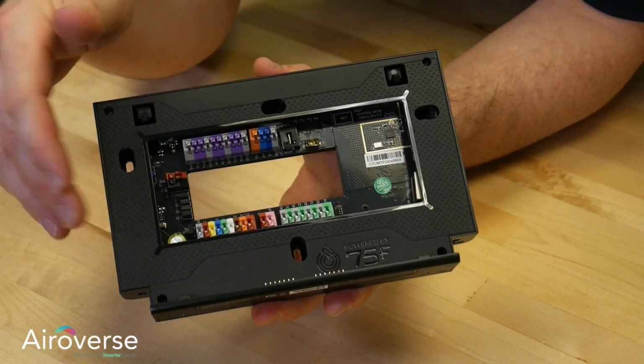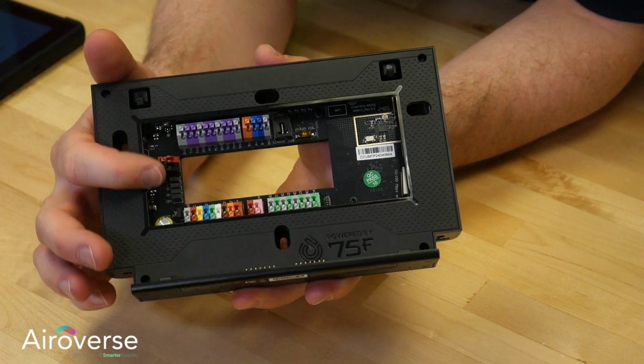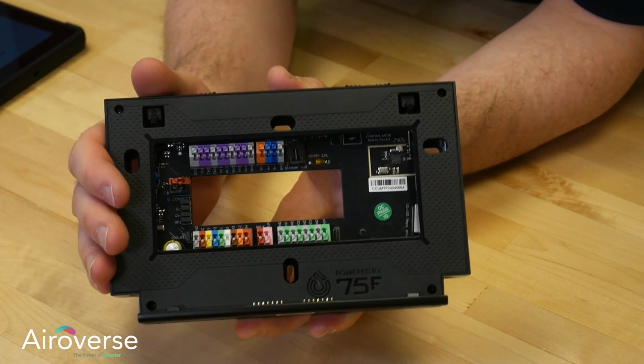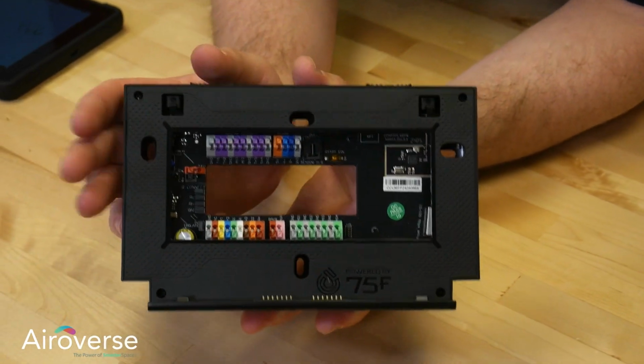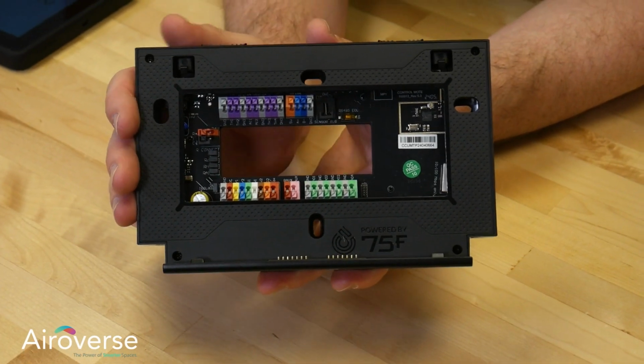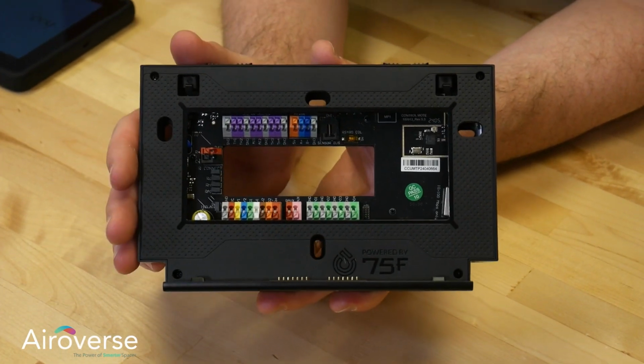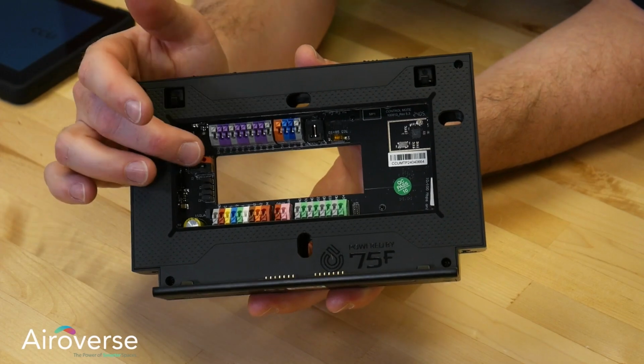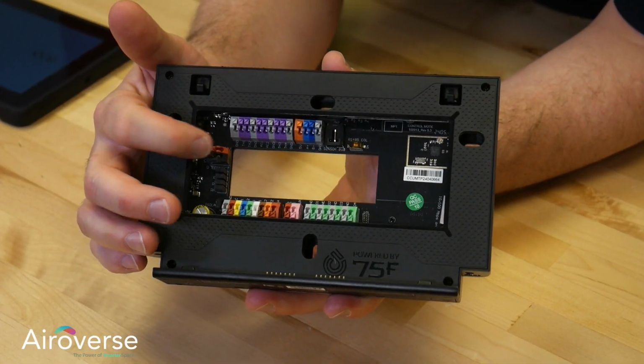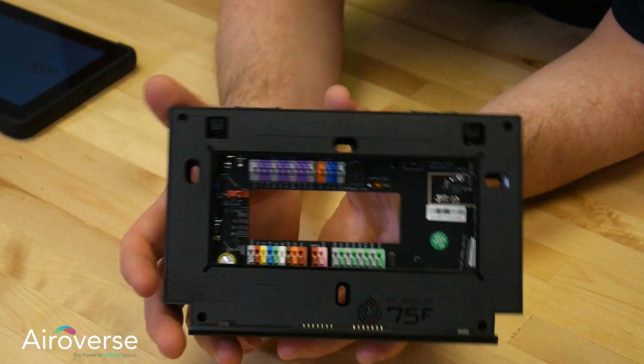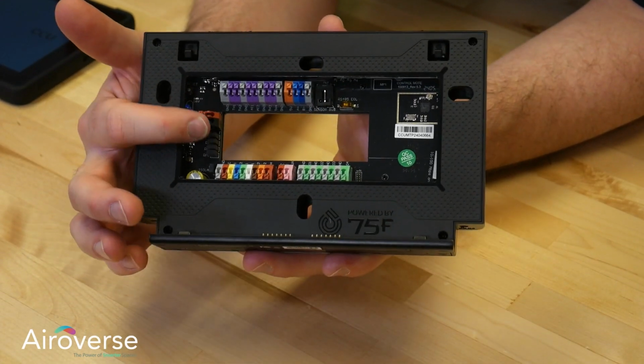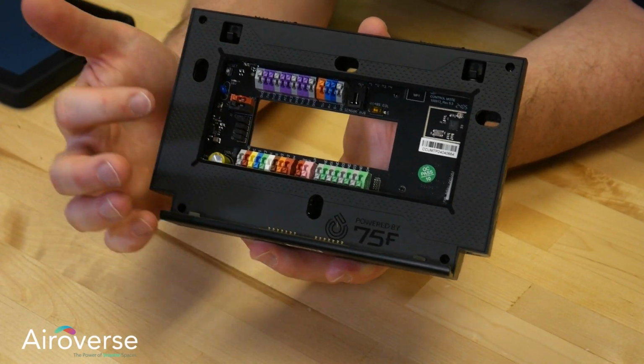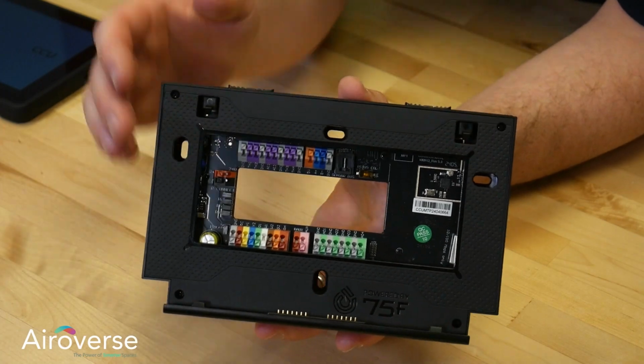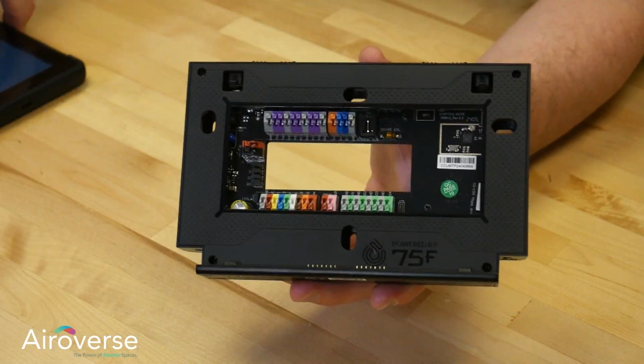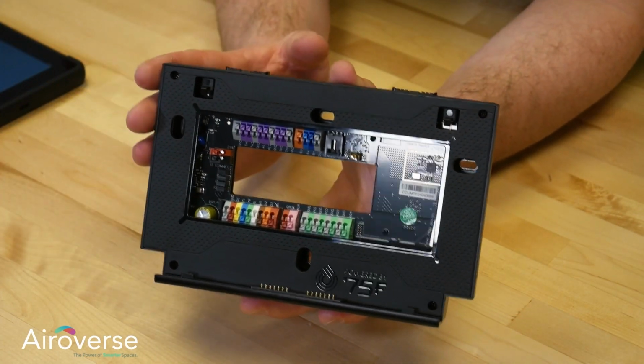When you're doing the wiring, depending on the type of AHU you're connecting to, sometimes you need dedicated power for the tablet. The tablet can draw up to 20 VA when it's charging. So if it's charging, or if your existing transformer doesn't have enough VA rating, you might want to pull the R connect jumper and isolate dedicated power for the tablet. That way you know that you're going to get a secure connection and you're not going to overload a transformer.